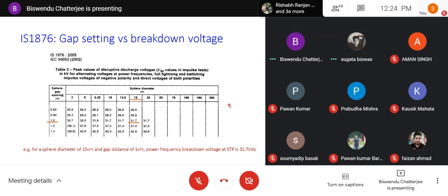What will happen, since the sphere diameter is increasing, if you decrease the gap, it will be parallel lines instead of the sphere, what you call the contour of the sphere. So the shortest distance will not be a single line, but somewhat parallel lines. Where the spark will occur, you cannot ensure. But I want to precisely measure the distance between the spheres at the line of the diameter where the distances are nearest to each other. Is this point clear?